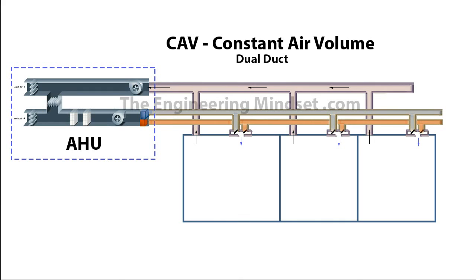If you've got one of these systems and you want to make it more energy efficient, you should ensure that a temperature reset is enabled. You'll need some advanced control points and temperature measurement sensors, but the temperature reset will monitor the air conditions required and reduce the temperature of the hot air stream down to the lowest acceptable temperature, while also raising the cold air stream up to the highest acceptable temperature — reducing the cooling load on the coil.